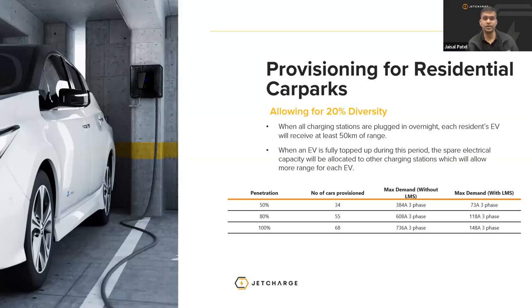So now we have a table that essentially details for a 68 car bay apartment complex, where when we have 50% penetration for that car park and there's 34 electric vehicles for the site, without load management, we would have 384 amps three phase, whereas with load management, our max demand drops to 73 amps, which essentially allows, as a worst case scenario, 50 kilometers of range for each resident at 73 amps, which is a lot more feasible in integrating into your current max demand calculations.